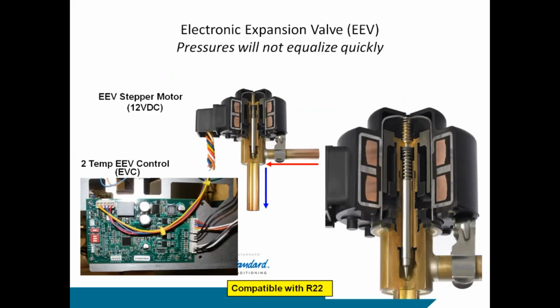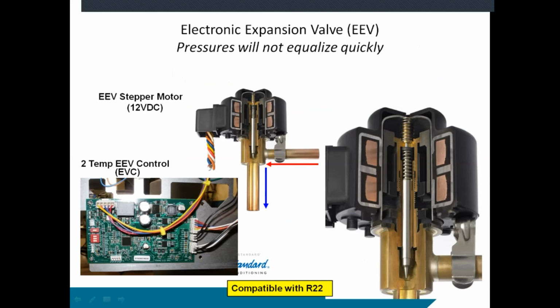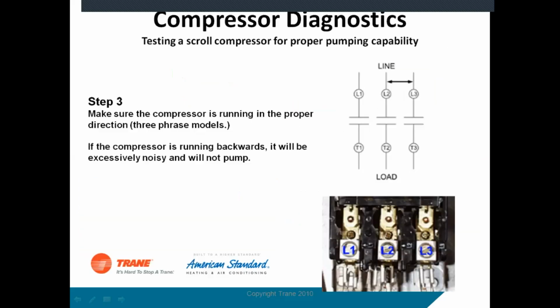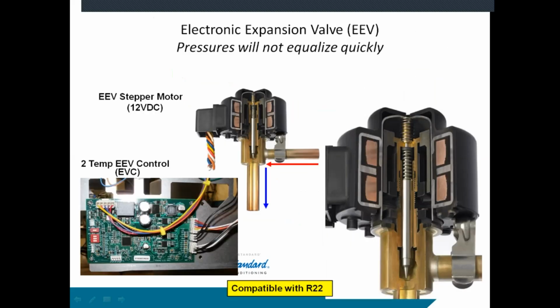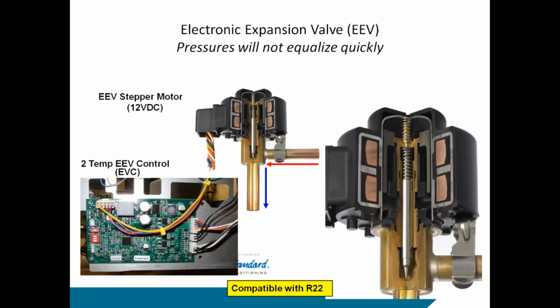Same thing with an electronic expansion valve, and you're seeing more of these in the field. If you look at an electronic expansion valve, we've got a stepper motor. We've got the valve, which is a needle valve, which is spun by the stepper motor. And then instead of using a capillary tube, we're using a thermistor and an electronic board to control that operation. It does the same thing. It meters the refrigerant the same way. And again, it helps protect the compressor from flood backs, but it's an electronic version of a TXV.